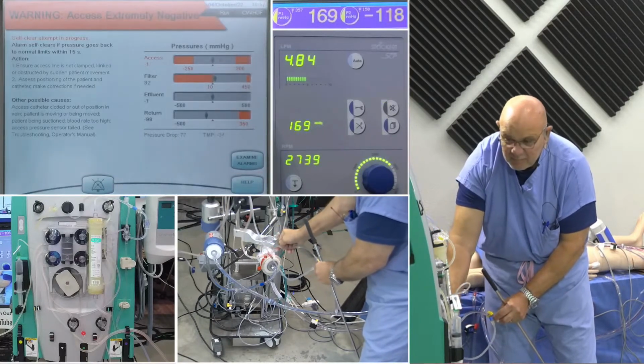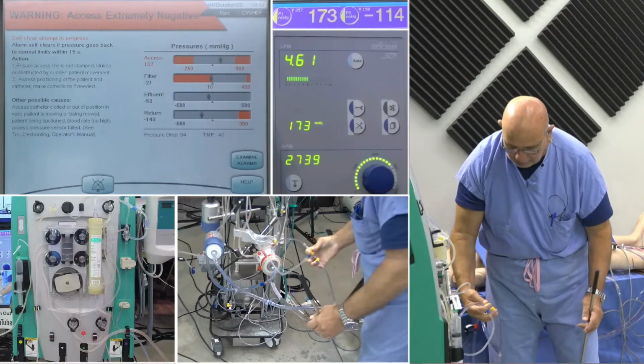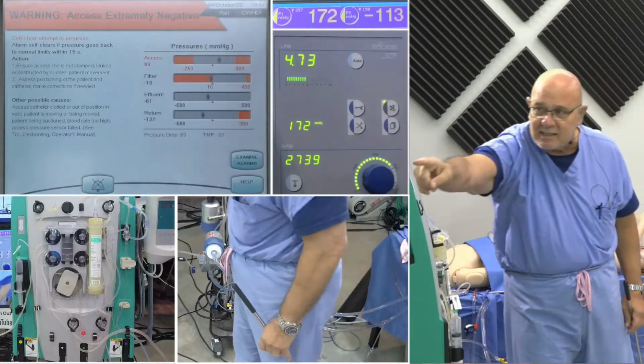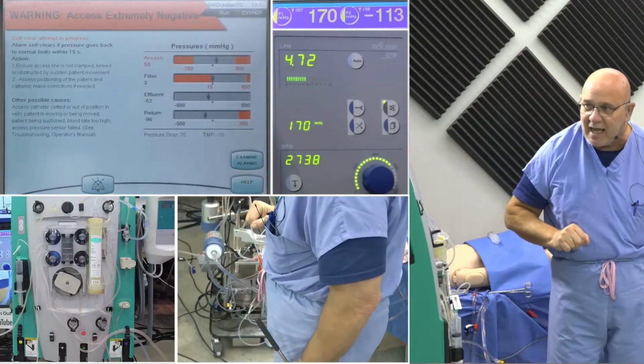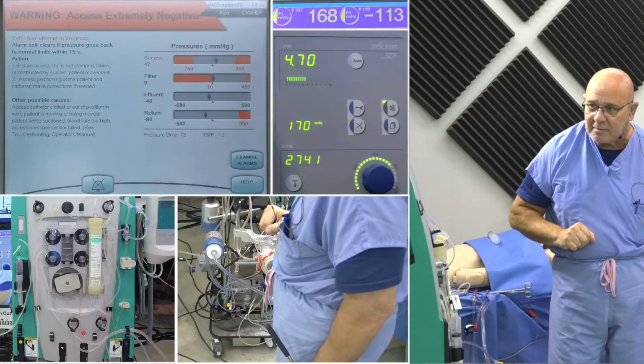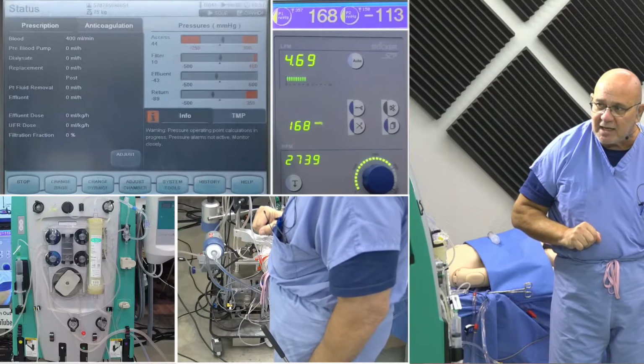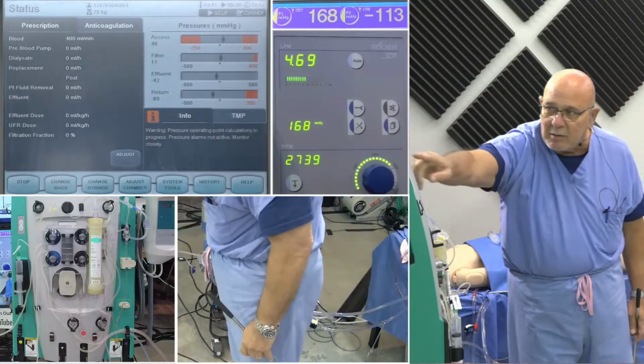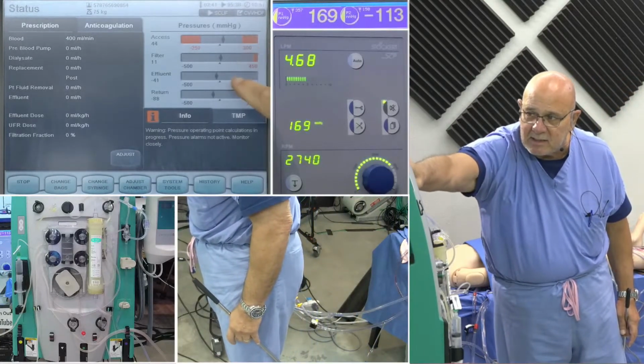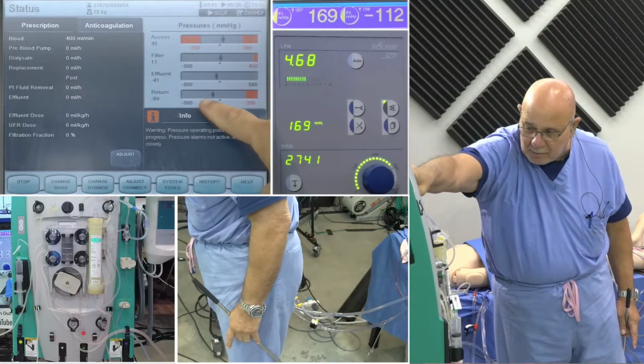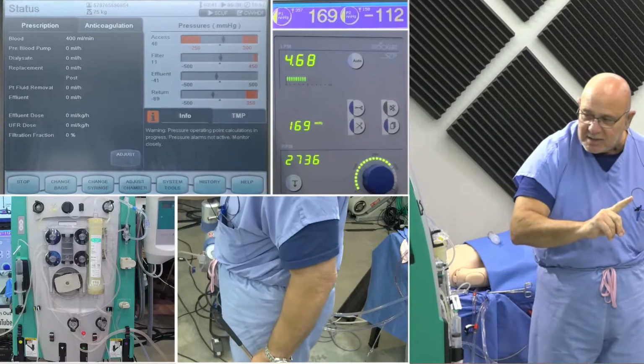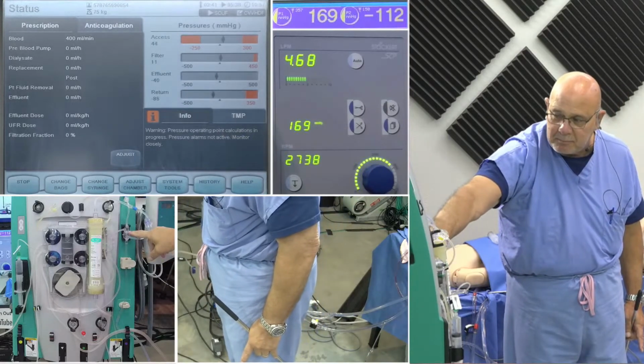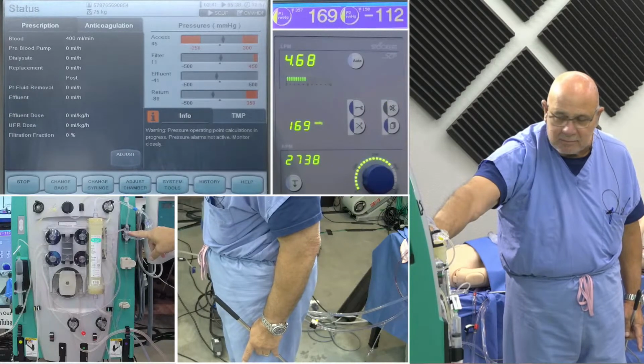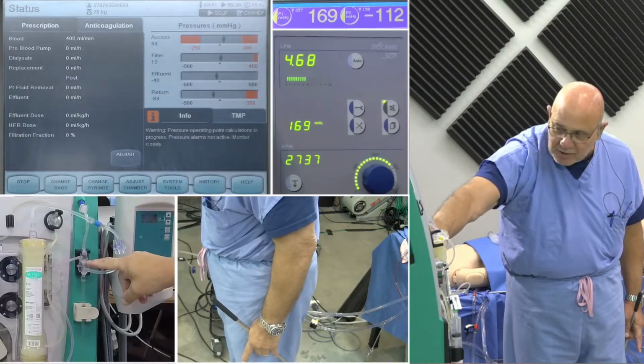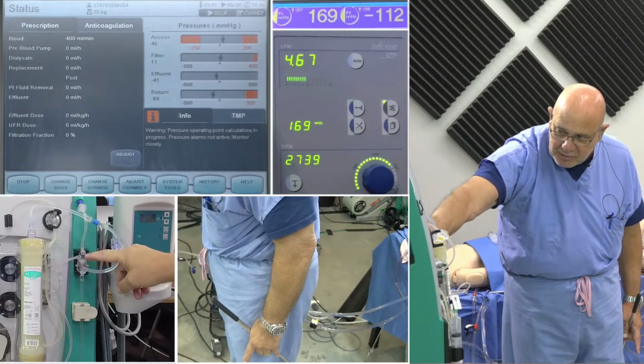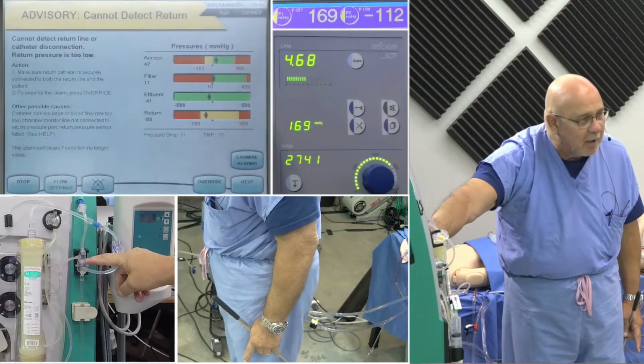There you go. And immediately we got an alarm, and that alarm says access extremely negative. Now it may reset itself, which it has. It has kind of come back. Check access, and you can see that now our access pressure is 46, our effluent is -41, and our return is 89. And if you can do this again for me, can you show this deaeration chamber right here, where my finger is? And look at how much lower. This was all the way up here to the top. You can actually see where it was, and look at how far it pulled it down.